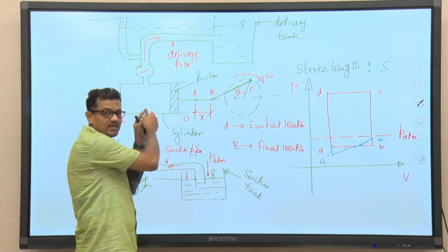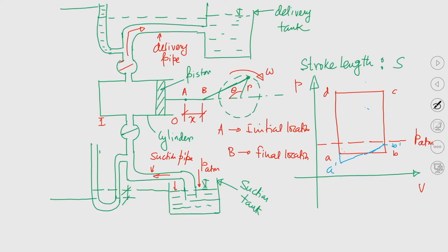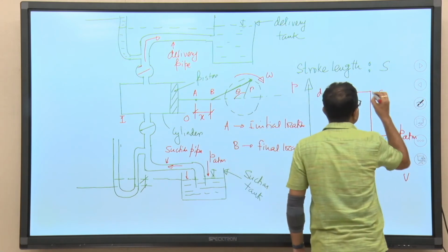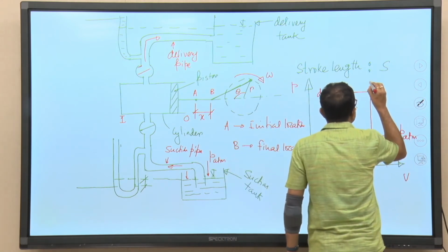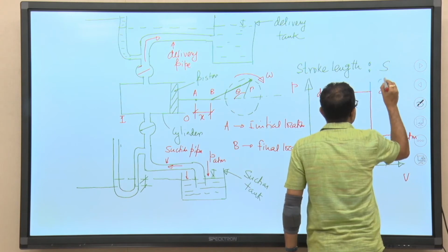We saw that at the beginning of the suction stroke we had acceleration; similarly, at the beginning of the delivery stroke the liquid inside the cylinder will have acceleration. As a result, that thrust builds up pressure inside the cylinder, so we need to modify this diagram again by this rise in pressure. So, this is C prime.